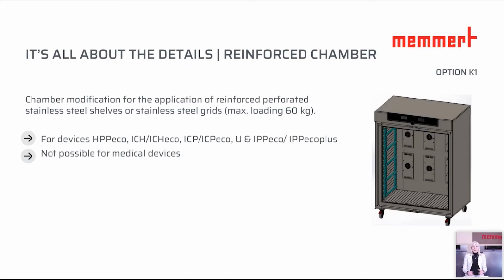Reinforced chamber. This is requested if the customer wants to operate and has samples which are very heavy. So if we have very heavy samples, then we go for reinforced grids and shelves, and then we also go for the reinforced chamber, and this is called K1. This is available for our units with 2 leaves, which means size 450 and 750, for example, incubator and oven. Here we have then the shelves or the grids with a maximum loading of 60 kilogram.